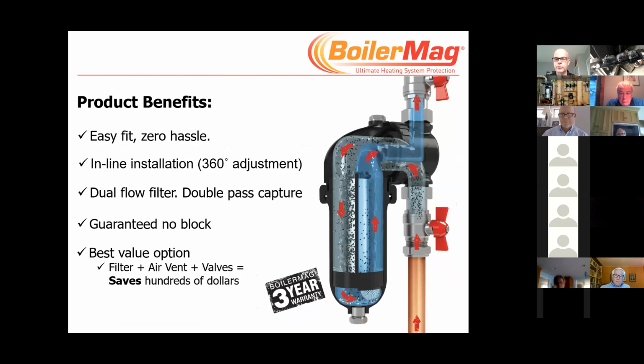This is a cross section of one of the BoilerMags in place, and you'll see how the actual vessel is split. You'll see some pictures of that later on. There's a plastic divider in the vessel, which means that the flow just can't pass straight through. It has to go down both sides of the magnet, which gives the magnet double the chance to take out any contamination. The valves come with it, like I say, so it goes through the valve, through the filter, back into the system, fully cleaned, and we're getting about 90+% first pass efficiency. But anything that passes it, we're going to remove. Dual pass, dual flow, guaranteed not to block, easy to fit.